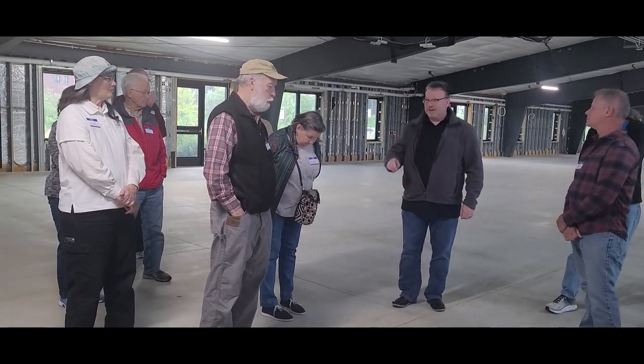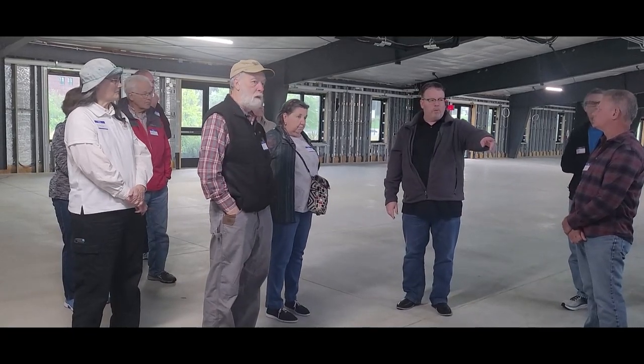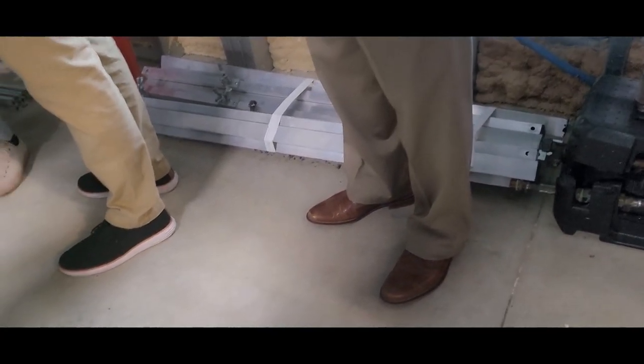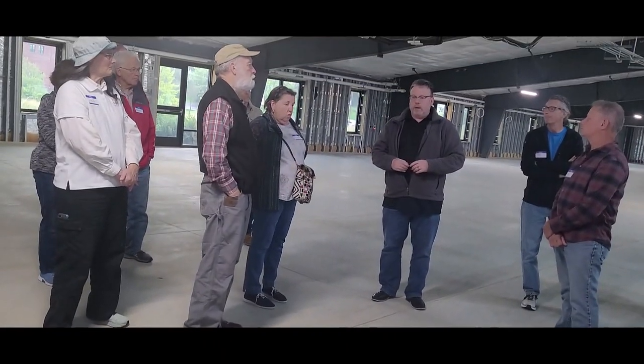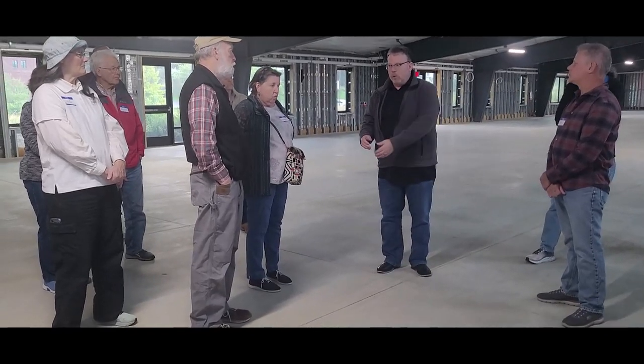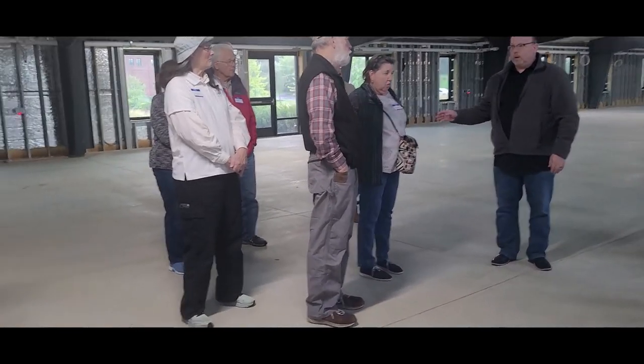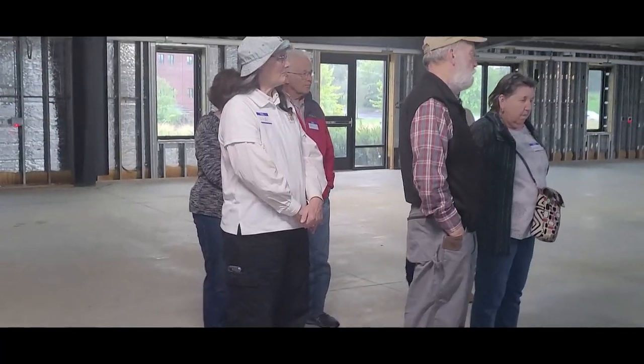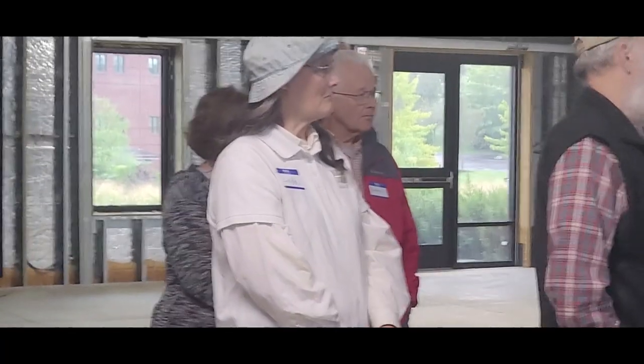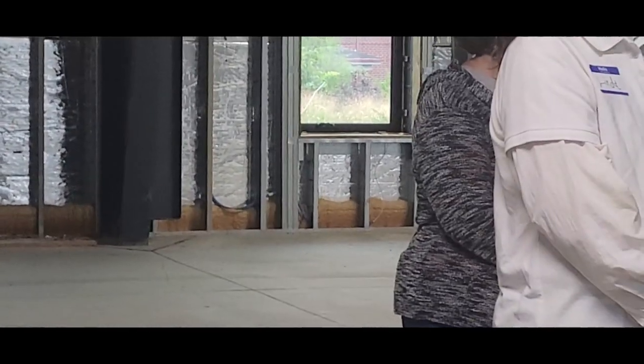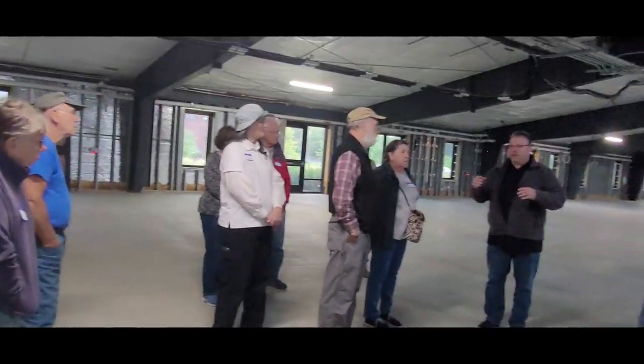Very good question. There is foam 8 feet in from the exterior. There is nothing under this floor, and that's on purpose. We found out that this building is heat load dominant. We ran all of our energy models, and we did run models with foam all the way through underneath the bottom of the floor. And what we found out was that the building, as designed as an office building, would consume less energy if the center of the building was coupled to the ground, because it cools more months out of the year than it heats.